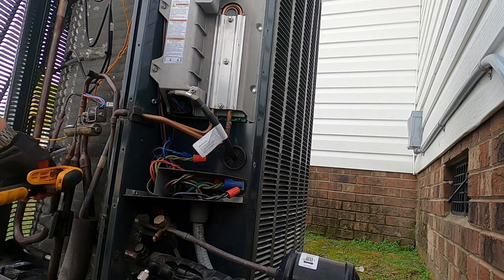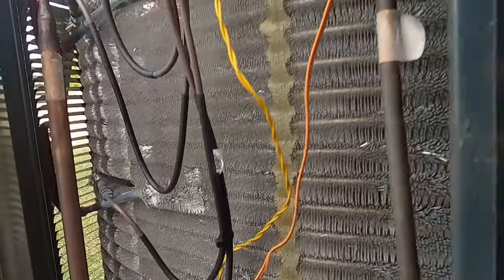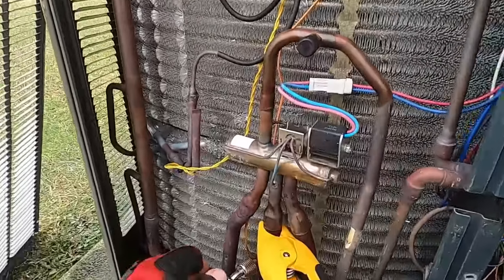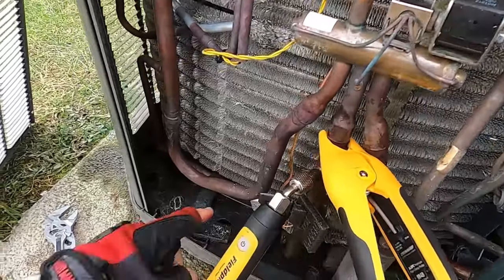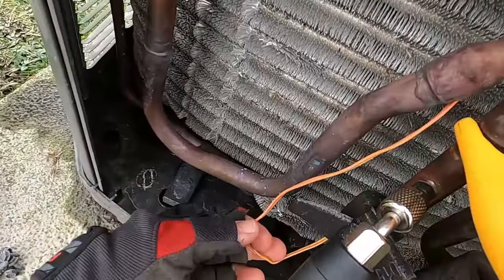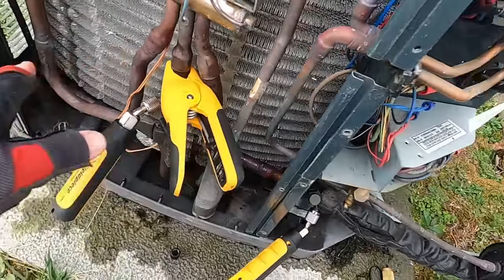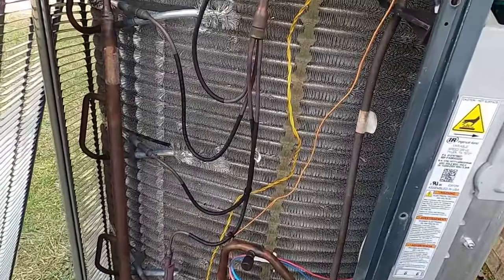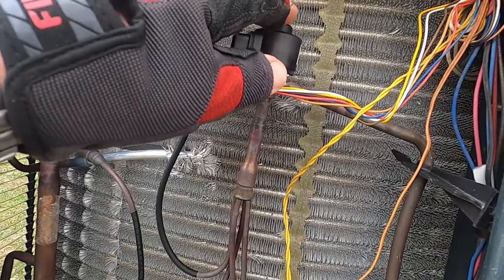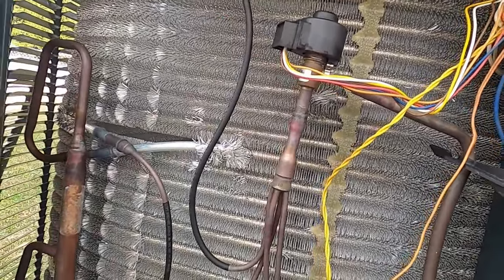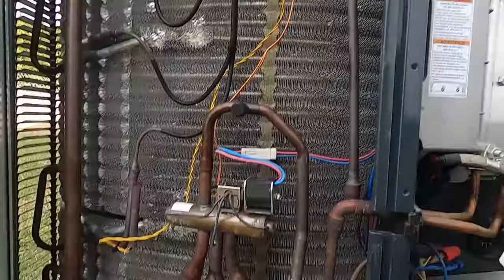But I want to test the defrost cycle, and then I'm going to check the pressure transducer right here, which is inside the unit. Make sure it's reading an accurate pressure, and then check this sensor down here, this orange one, so I know that this thing's measuring proper superheat out here in this outdoor unit and controlling this EEV properly. Could just be a bad sensor.